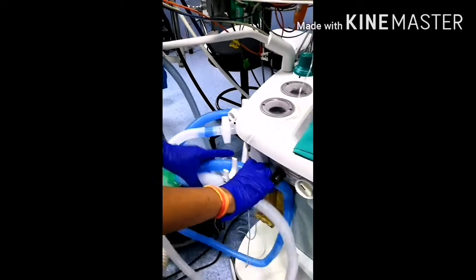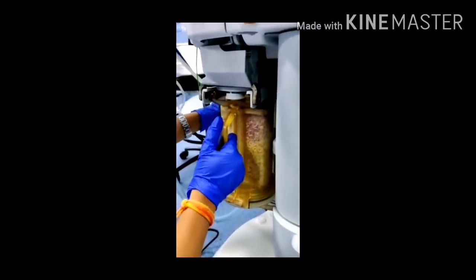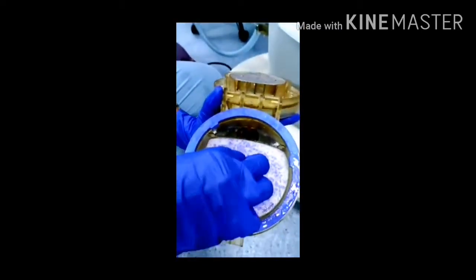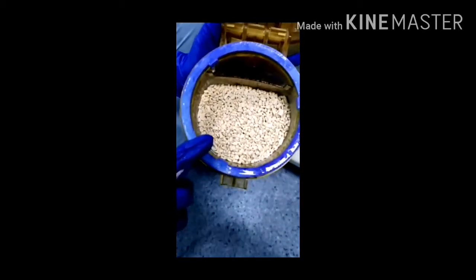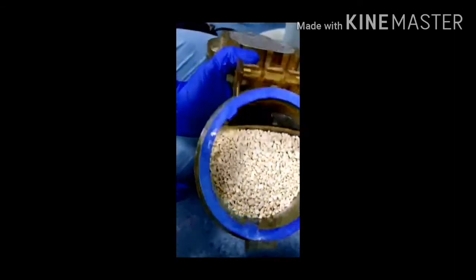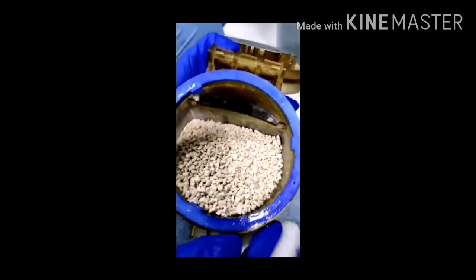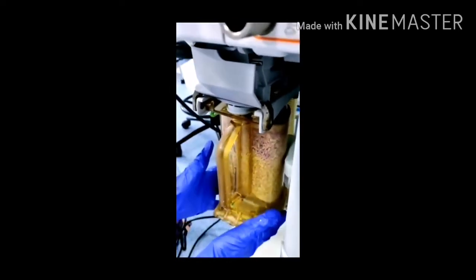Okay. Coming down, this is the soda lime canister which absorbs the CO2 gas. So to change the soda lime, you have to open this switch, open the jar. You can see there is sponge inside it and there is soda lime. While replacing it, you have to remove it in a yellow bag, change the sponge if it is wet, clean the canister from inside and also the exterior so that there is no gap and there is no leakage from the soda lime canister. After placing the sponge, there is a sponge at the bottom also. Put in the soda lime, place the sponge, press it tightly and then lock the canister. While placing it, slide it through the railing and just tighten it. So this is how the canister is placed. Okay.